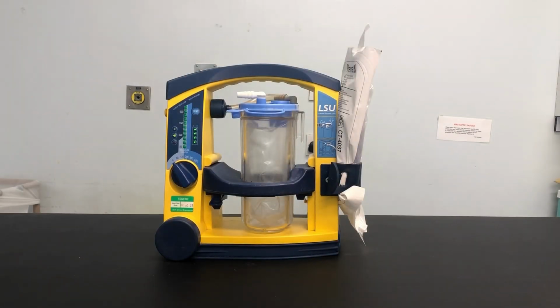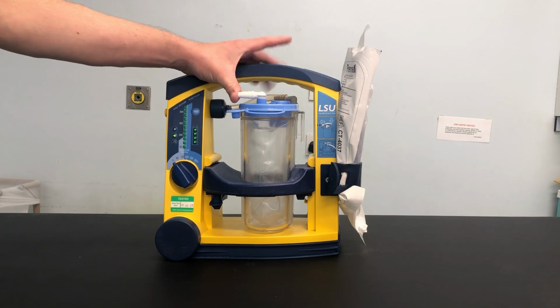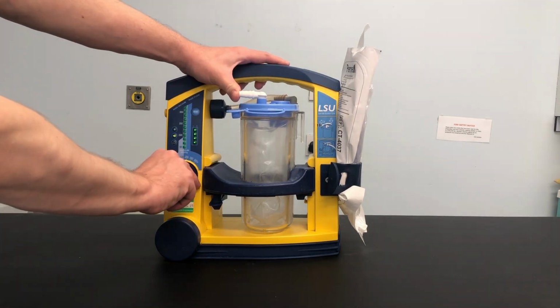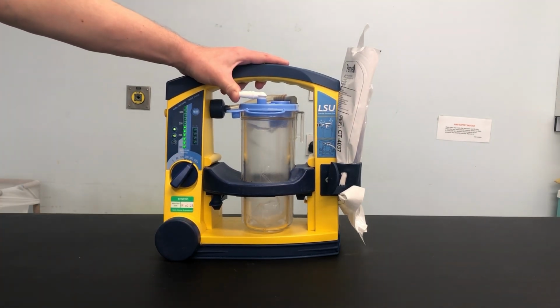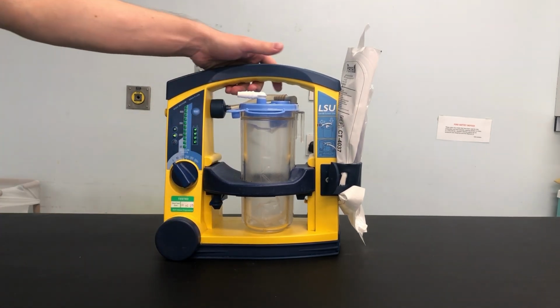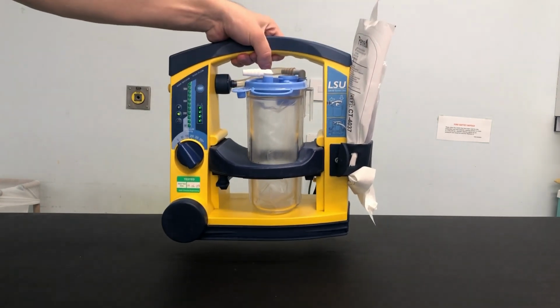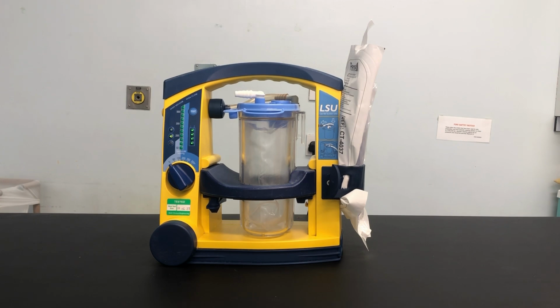Block the white angle connector patient inlet and turn on the LSU. Vacuum will build up when all the parts are assembled correctly. Total weight of the device is 4 kilograms. The LSU has a carry handle to allow for moving and handling of the device. The LSU must be operated in an upright position to prevent overflow of suction materials getting into the device. And if in doubt regarding the moving and handling of this device, contact your local moving and handling link person or the authorized trainer for this device.